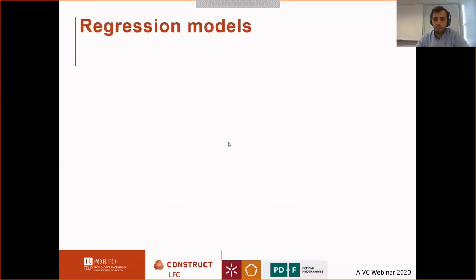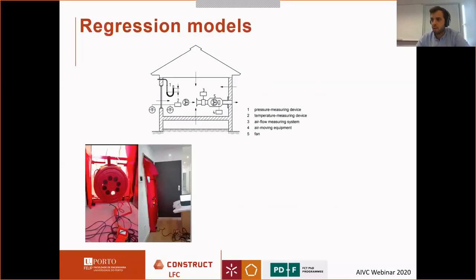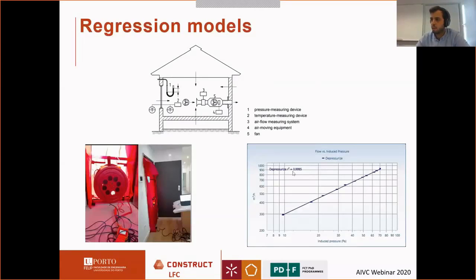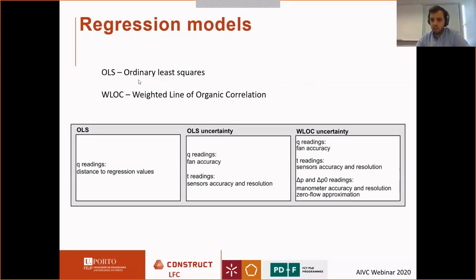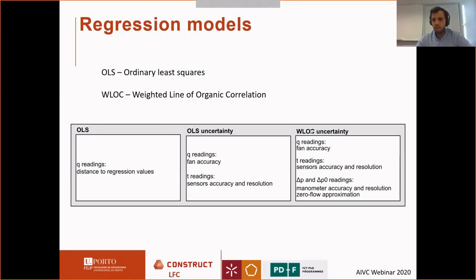To make this data treatment more robust, we can use different regression models. I'll present three of them. The first is used in the current ISO standard and uses the distance to the regression values of the airflow, caring for the variance of these values. The second is the same type but uses the fan accuracy for each point — the uncertainty in the airflow based on the fan accuracy and the resolution of temperature sensors. The third is the weighted line of organic correlation, which associates weights to the pairs of airflow and pressure differences alongside the accuracy of the fan and temperature sensors.